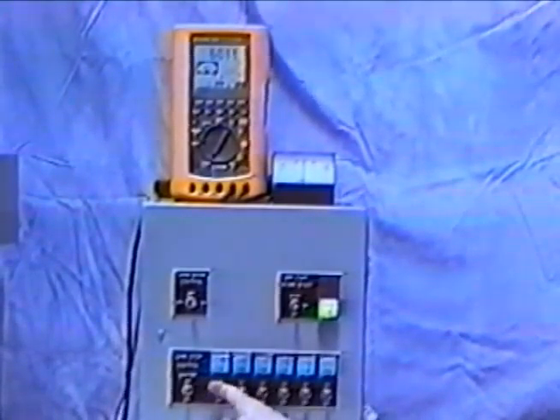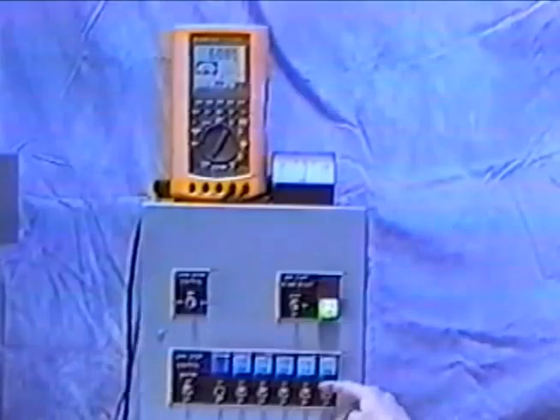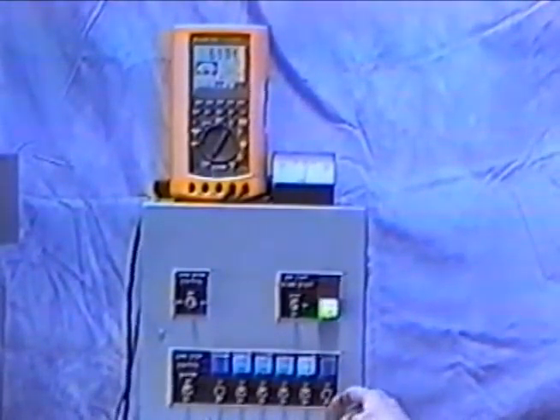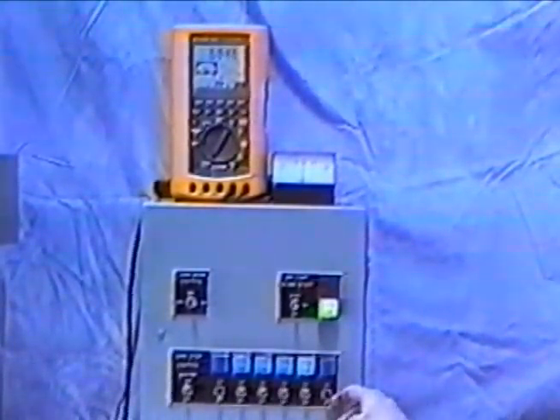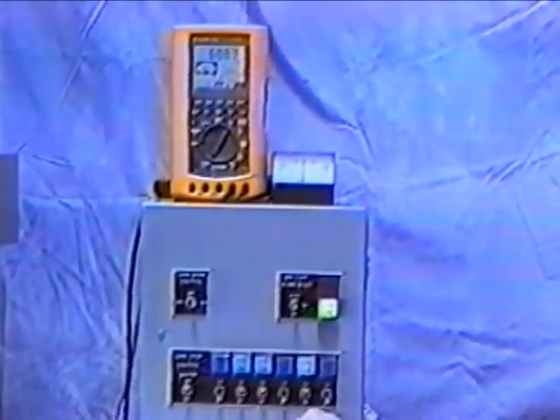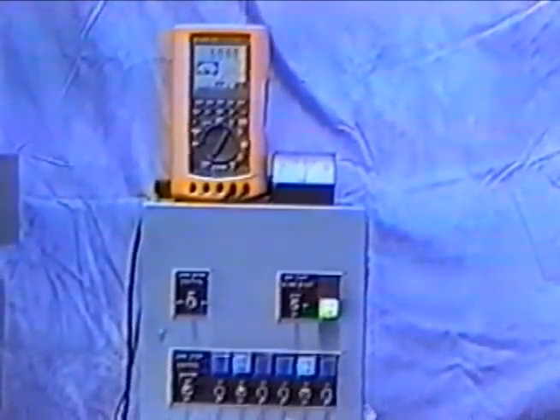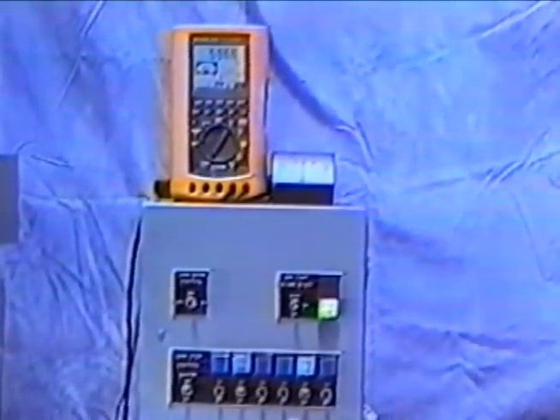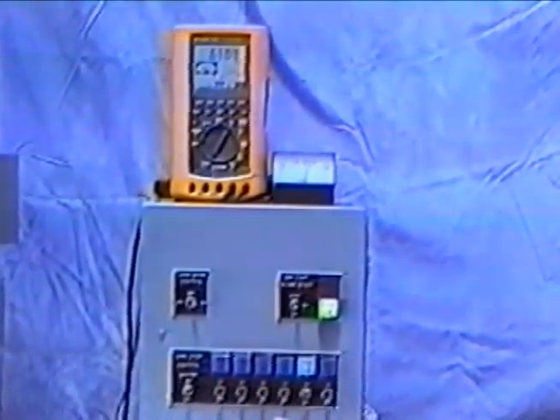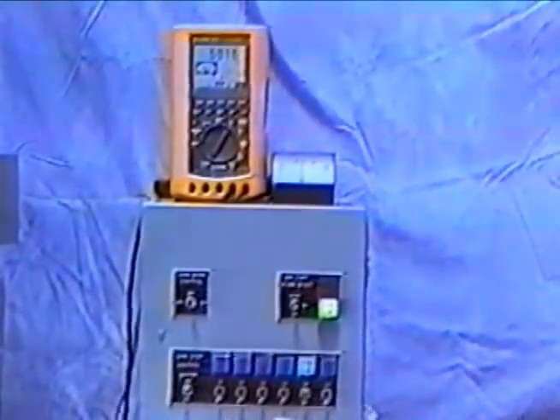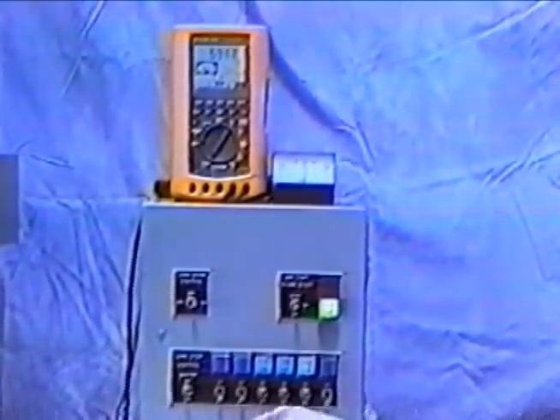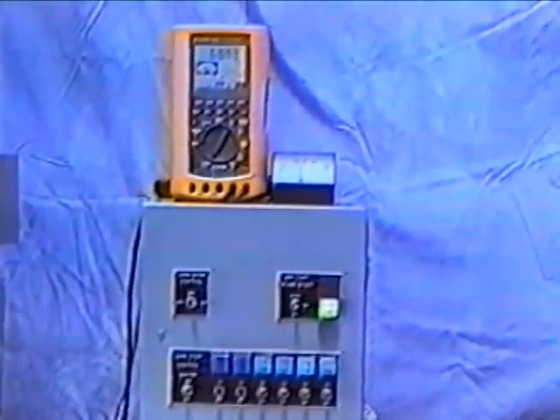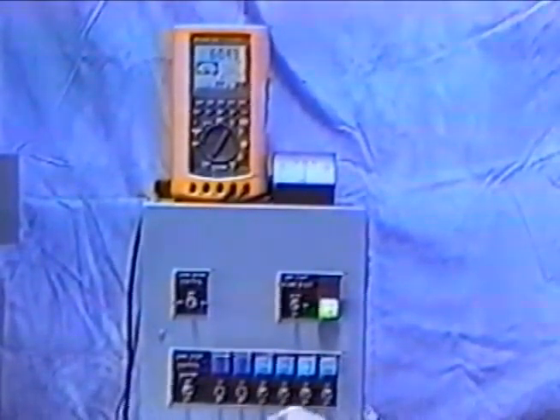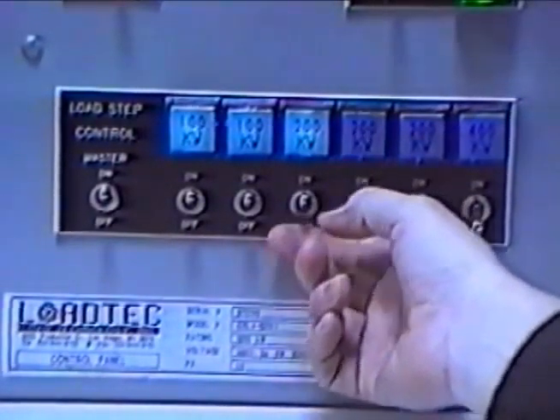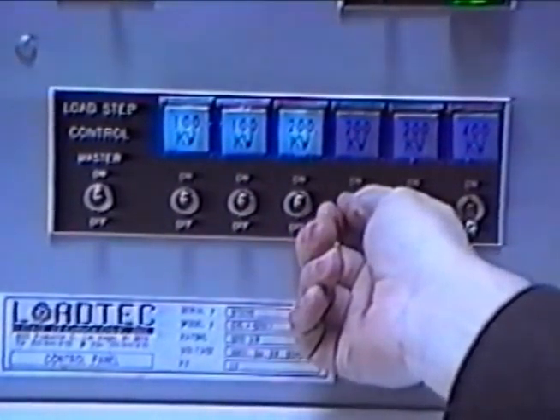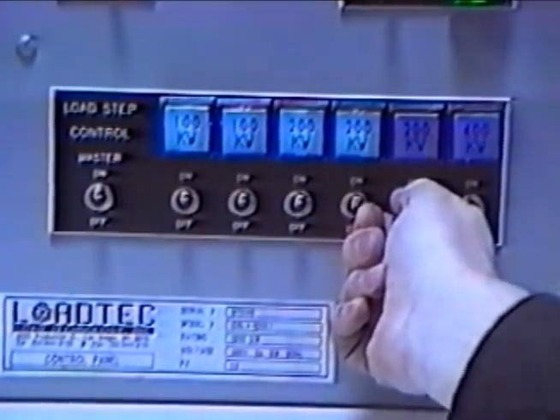The Innovator control lends the genset an extremely reliable operating platform, having true deterministic control, an absolute necessity in turbine operation. With the Innovator control, GPS has simplified what in the past has been a very complex and cumbersome operation. Featuring new standards for reliability in process control, the Innovator offers a direct connection between the I/O and processor. The system allows for off-site monitoring, troubleshooting, predictive maintenance, and trend monitoring with compact size, stability, superior processing, and control. Even larger load changes are perfectly manageable for the Innovator to accommodate as well. In fact, the Innovator's control functions are actually faster than some of the mechanical functions on the skid.